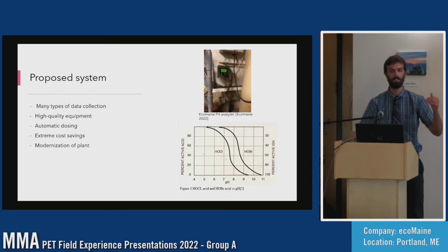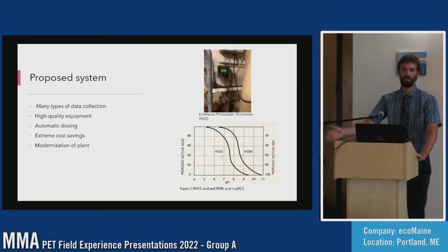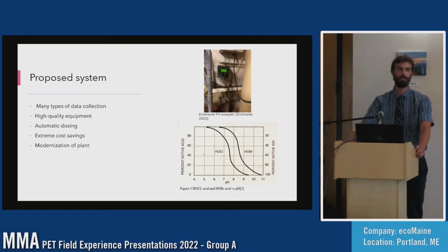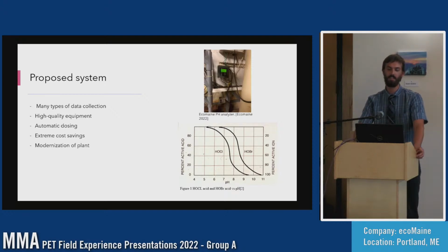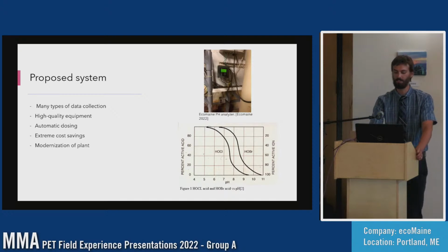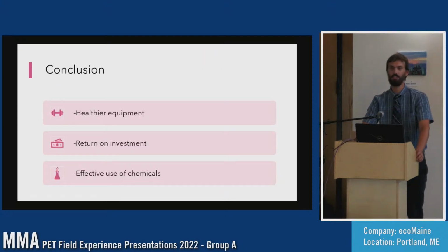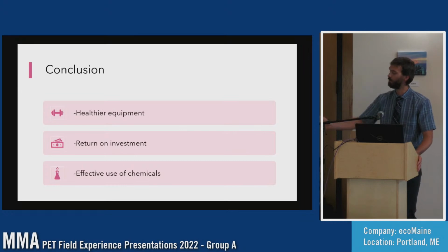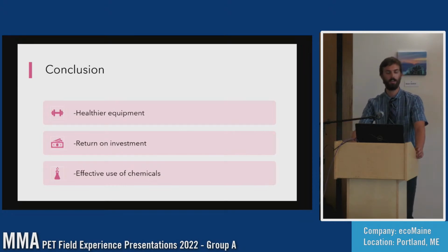Obviously, this would only be while the turbine's out, because when the turbine came back, we'd be able to run at higher efficiencies. But ecoMaine would still have the benefit of having a new chemical dosing system and save money on chemicals and time for the operators dosing it manually. So in conclusion, having less algae running through the equipment will also make healthier equipment, as well as extending the life of the cooling tower.